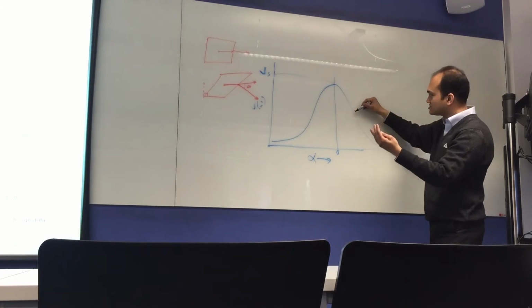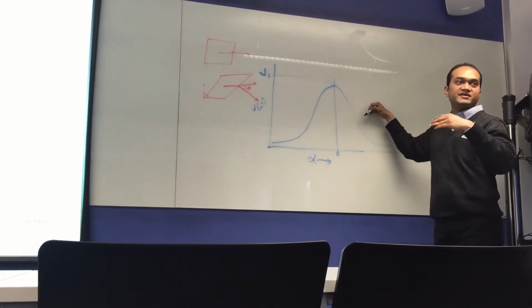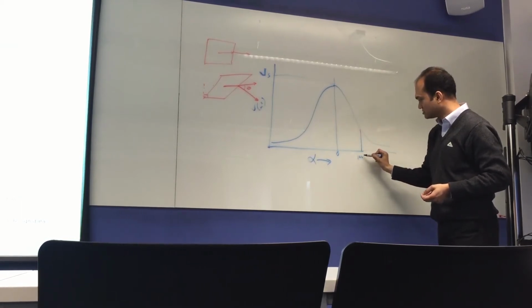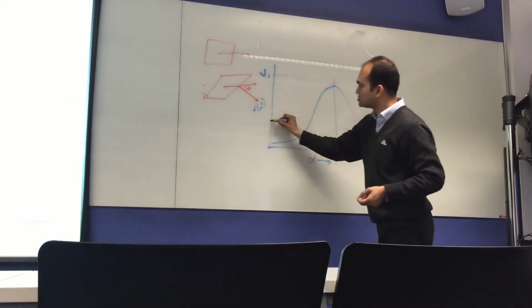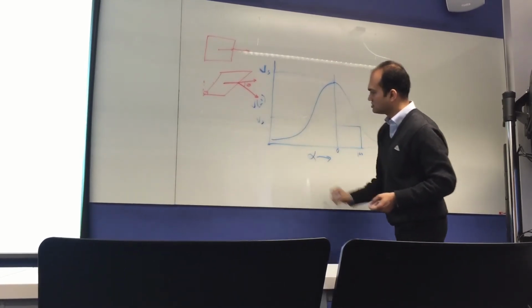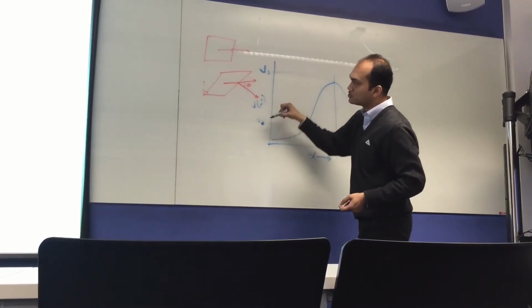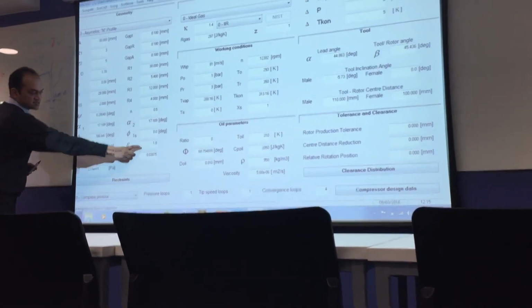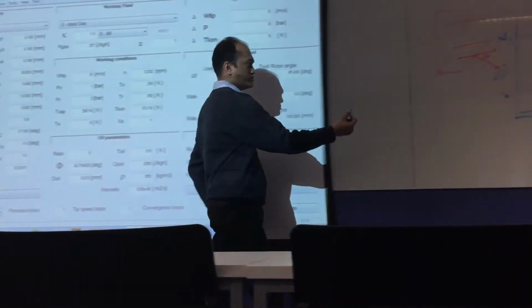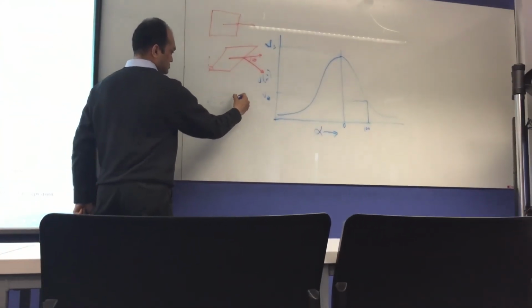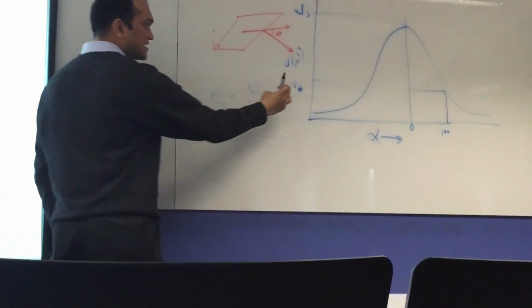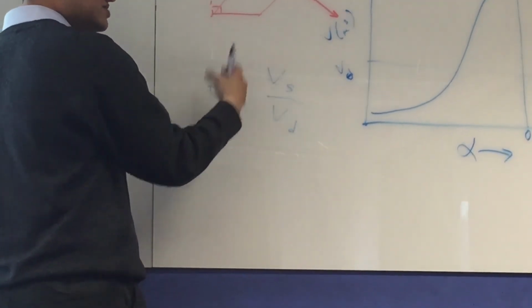And then when the compression starts, you have an option of opening the discharge at some angle. Depending on at what instant you open it, you will get certain internal pressure. So let's say you're opening here at 100 degrees. And this volume corresponds to V discharge. So these are the two angles, Vs and Vd. And this epsilon is the ratio of the two. So you have an option of selecting the angle or selecting epsilon, which will define that angle.